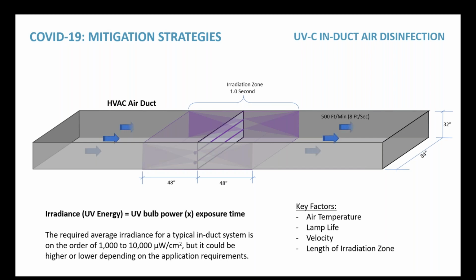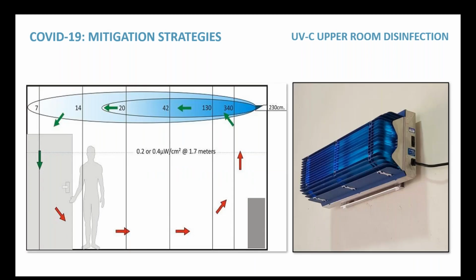And different levels of irradiance are going to be available from different UVC system types. So you have to look at how much irradiance am I putting in? What is that irradiation zone? And you have to make these decisions because, in this example, we've shown an irradiation zone of 1 second. They can be shorter than that. They can be longer than that. In this example, you're looking at approximately 8 feet of straight length of duct that's required. So it's something that needs to be taken into consideration when you're thinking about using this on an existing system, because you may not always have that amount of space.